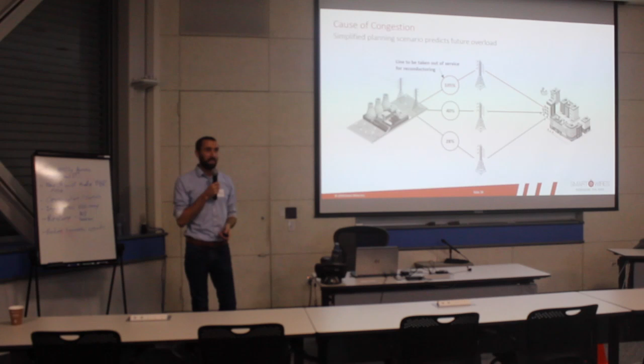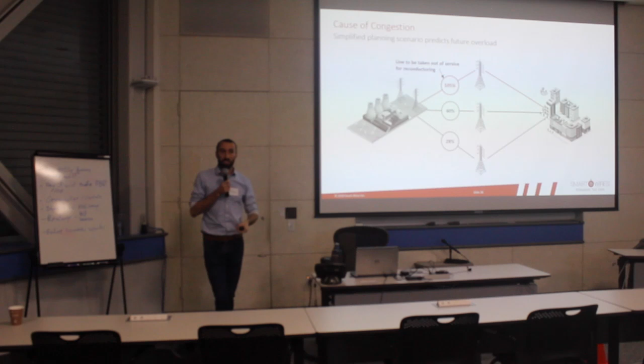Let's jump ahead and say the utility doesn't want to use SmartWires to resolve that overload, and instead needs to reconductor that line. This might not even be due to an overload—it could simply be that the line is too old. It's not uncommon; PG&E has lines that are 60, 70, even 80 years old on their system. Eventually, structurally, they just want to replace them. The challenge is when the utility is able to do that work.